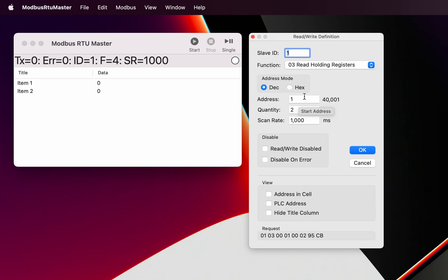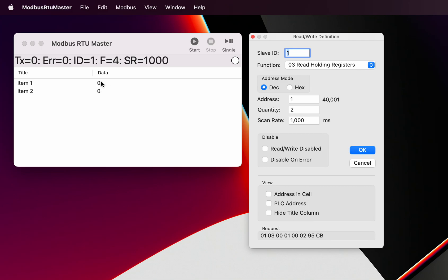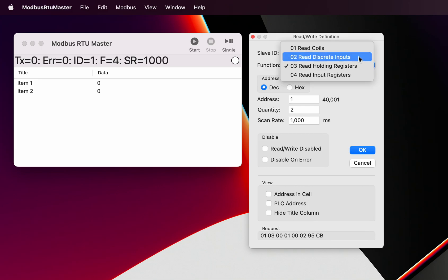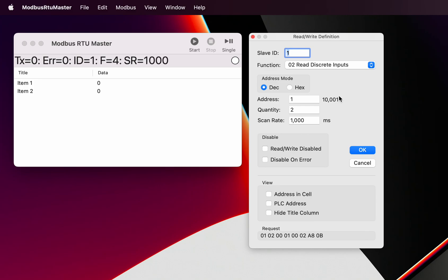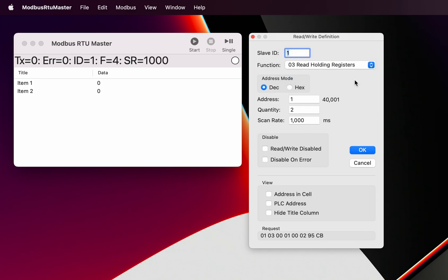The first one we'll read from address one. We've got the ability to view these addresses in hexadecimal or decimal. We've also got the ability to select whether we want to see the address in the cells. We call this the plc address - this is the raw address, this is the actual PLC address according to Modicon standards. As we change the function, that address here actually changes, so those familiar with Modicon PLCs will see that.